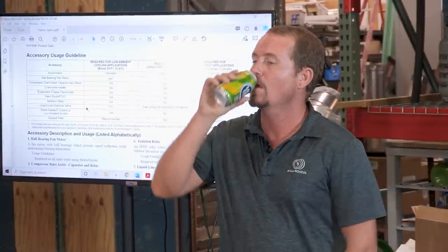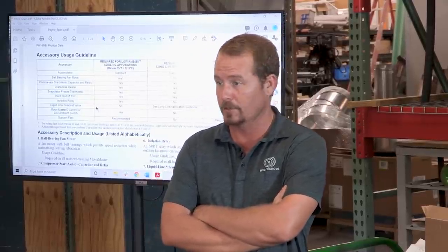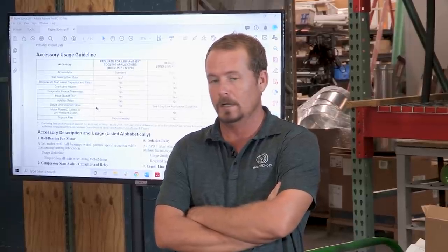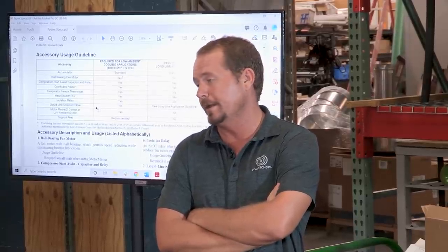In the winter, you may still be getting a cool call. Like if you're a commercial building, you have a lot of internally generated heat. And you have to be trying to run your system when it's 30 degrees outside. So if you're trying to run the system when it's cold outside, which you have to do in a lot of applications, server rooms are a really good example of that. We'll run into that from time to time. Even some people will try to run it in a media room where there's a lot of internal heat generated, and they may want it all year long.